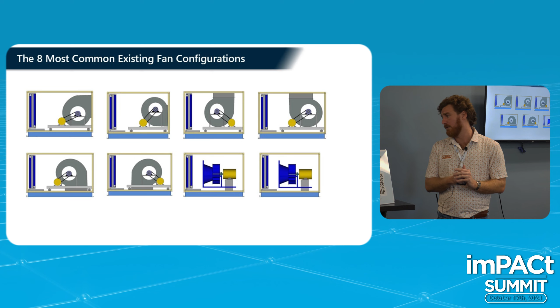If you're tearing this one out, and this is your outlet, you probably want to move your fan a little closer to the coil, and make sure you have enough room for the airflow to work appropriately. Another thing you could do is add some sheet metal to go over that, and move the outlet as well if you tore it out and put the Q-PAC fan in.